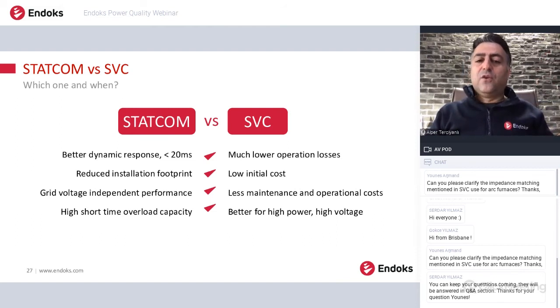On the STATCOM, since we are using IGBTs, we are using higher switching frequencies. This means that on the STATCOM, switching and conduction losses are high compared to SVC. And SVC's initial cost is lower, and it needs less maintenance and operational cost. And SVC is better for very high power and high voltage applications.